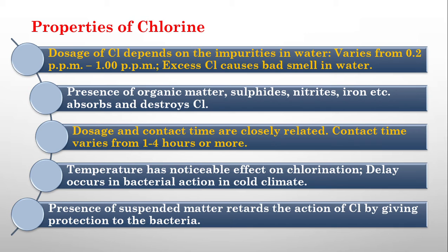And if suspended matter is present in the water, then it can shield the bacteria, okay, without making it in contact with chlorine. Okay, when suspended matter is there, we have to remove the suspended matter first, and after that only we can do the chlorination. Otherwise the bacteria will be shielded by the suspended matter, and proper disinfection will not take place.